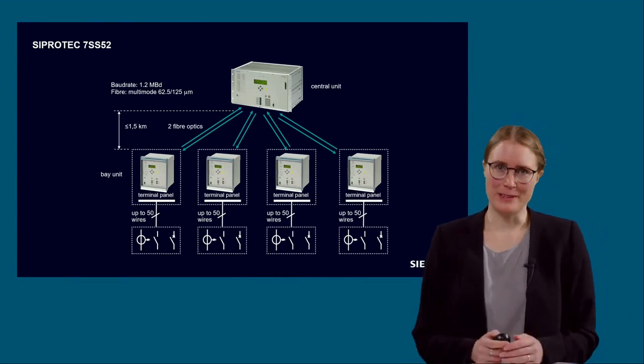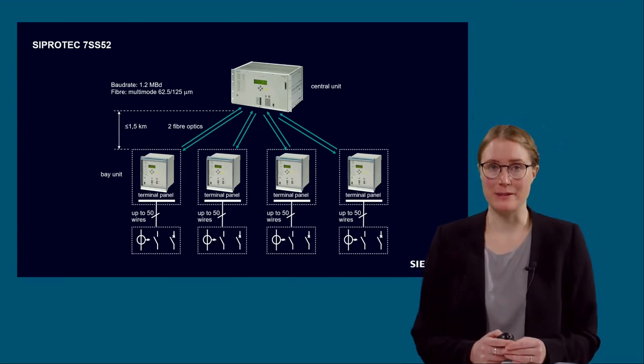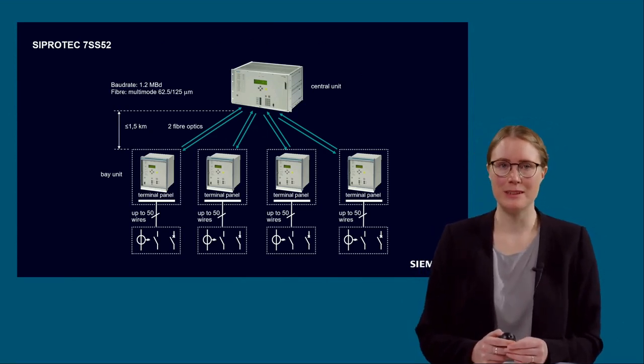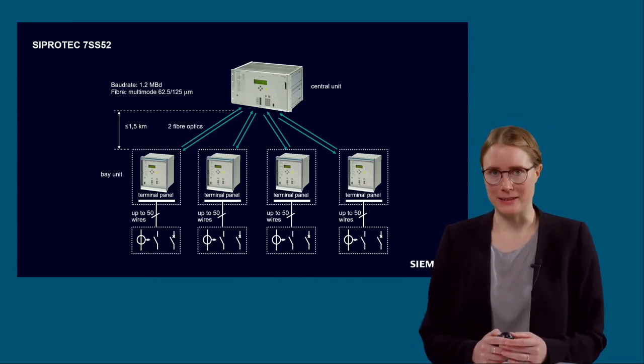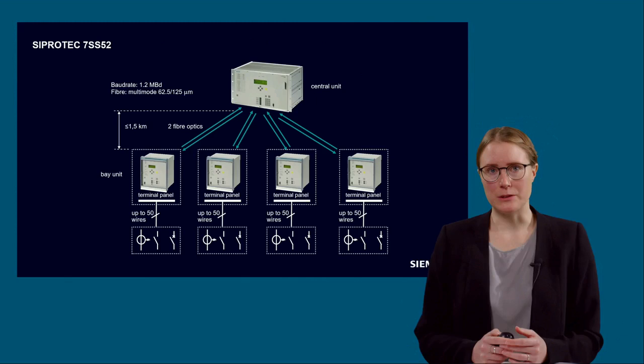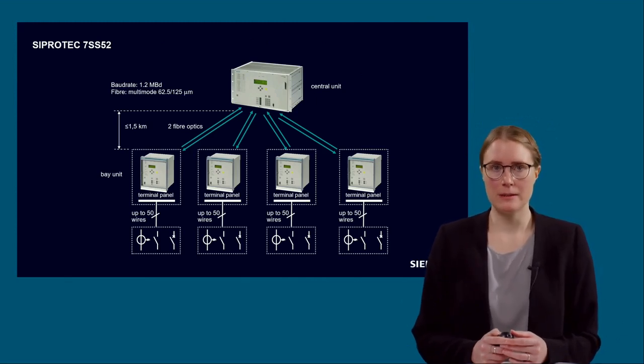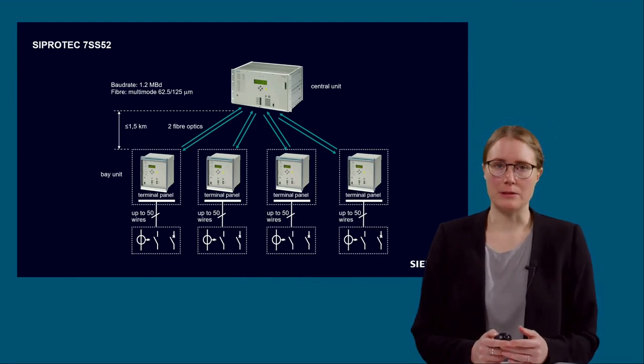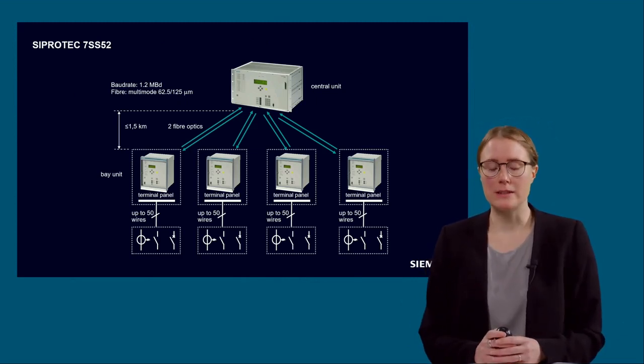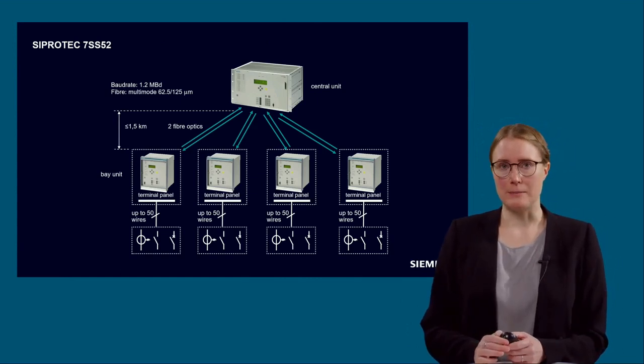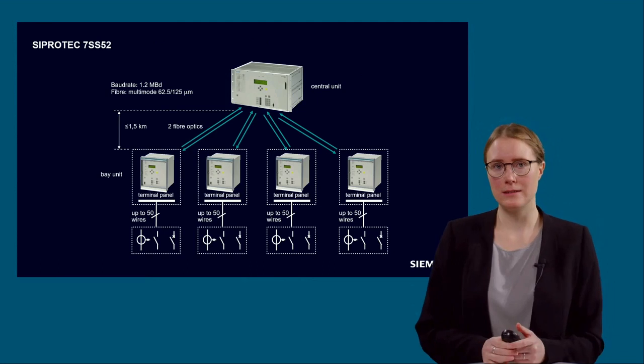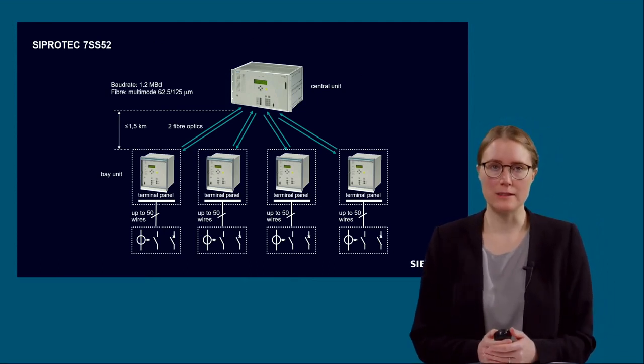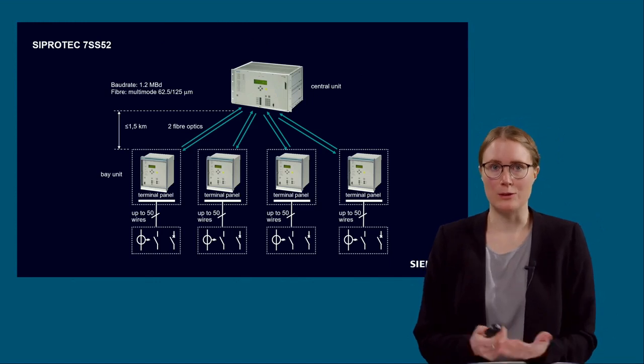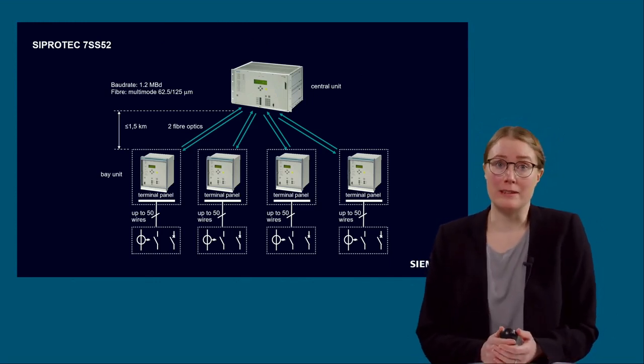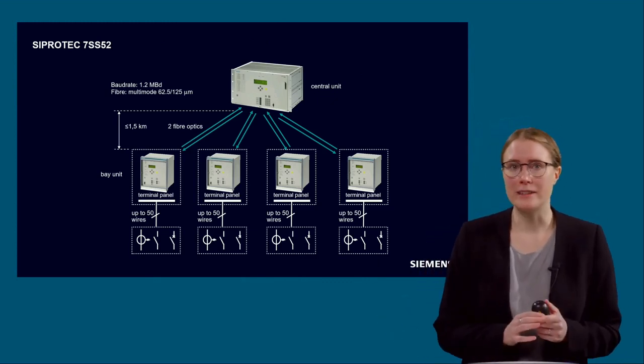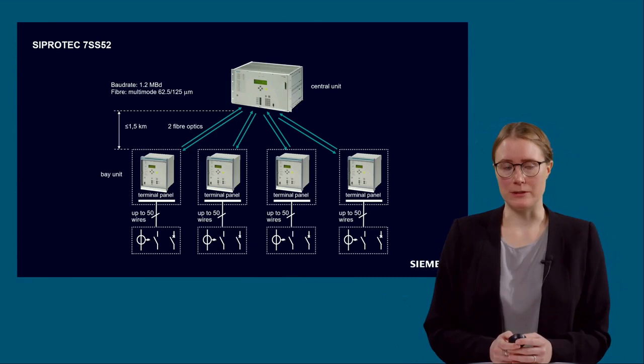This slide may be familiar to some of you who already have experience with the SIPROTEC 4 7SS52. For those who are new to this, I would like to tell you a little bit about it. The 7SS52 is a distributed busbar protection solution. This means the process signals, for example the current transformers, the circuit breaker, the disconnectors, are connected to the bay unit. This is meant with the symbols on the bottom of the slide. The bay units are then connected to the 7SS522 central unit. So the 7SS522 is kind of the brain of the system, collecting and processing all the data from the bay units and doing the differential protection.